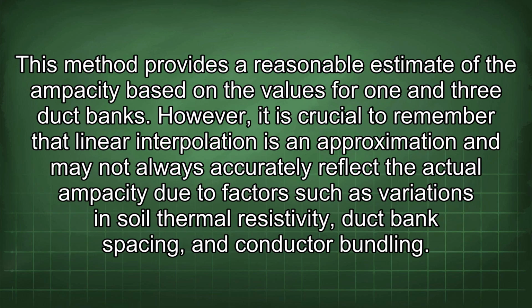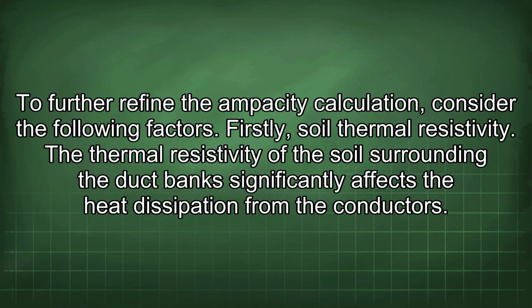This method provides a reasonable estimate of the ampacity based on the values for 1 and 3 duct banks. However, it is crucial to remember that linear interpolation is an approximation and may not always accurately reflect the actual ampacity due to factors such as variations in soil thermal resistivity, duct bank spacing, and conductor bundling. To further refine the ampacity calculation, consider the following factors.